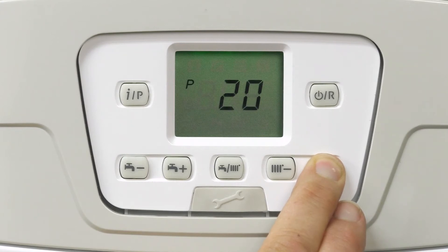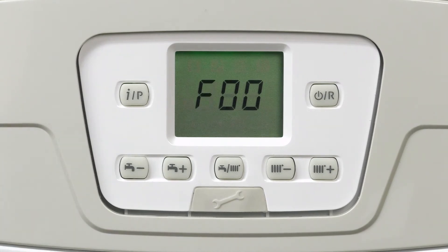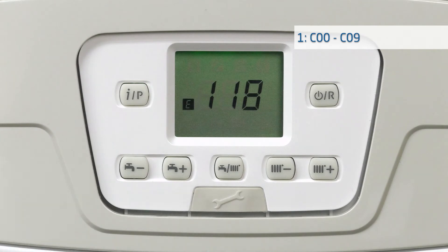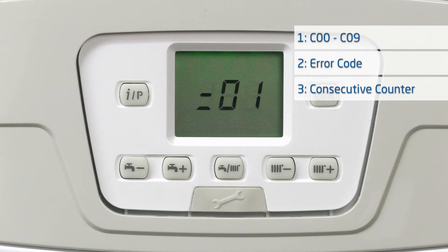Once there, three different numbers will flash on the screen. The first one will be C00. This is the error storage number in order from C00 to C09. The second number flashing is the actual error code. The third number is the consecutive error code counter of the same error, which tells you how many times consecutively this error has occurred.